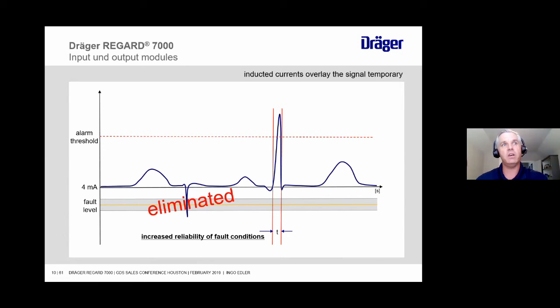Or if we're competing with a safety PLC, you can program that feature in there, but guess what? The guy who programmed it goes away 3 years later, you want to put a little alarm suppression on that detection point, and now you've got to call somebody in, and pay some engineer to come in and reprogram that PLC. Versus if you had the Regard 7000, you just go in there and configure that option versus having to program it. It's a big difference in user ease of use for our system versus using PLCs or DCS systems. So we eliminate that and reduce the number of false gas alarms.